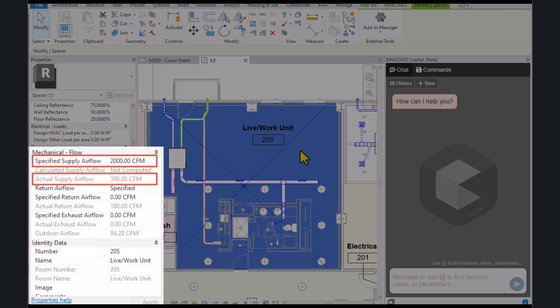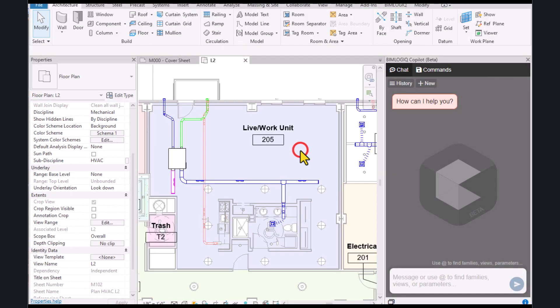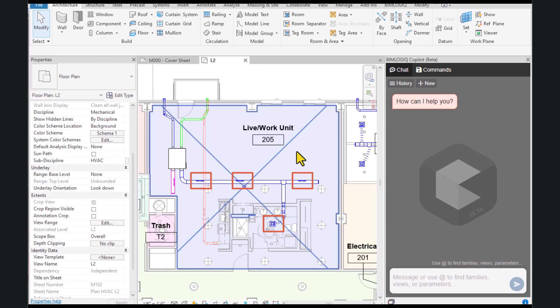Therefore, we want to automatically read the specified supply airflow value from the space, find the number of air terminals in that space, divide the value equally among them, and assign the resulting flow value to each air terminal.